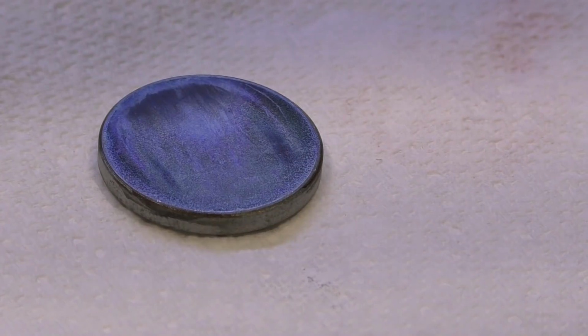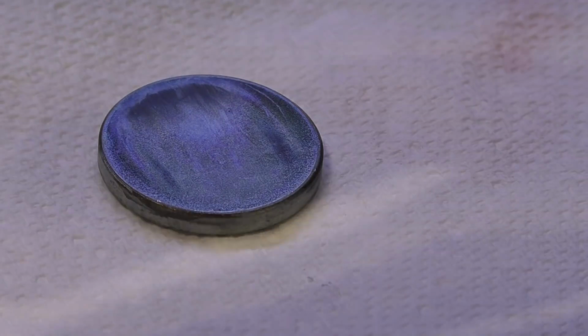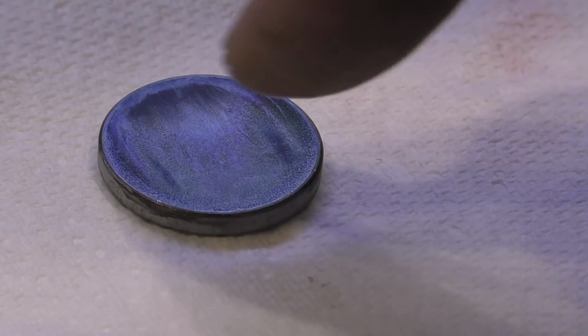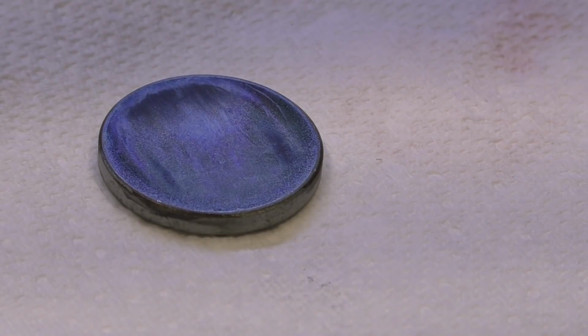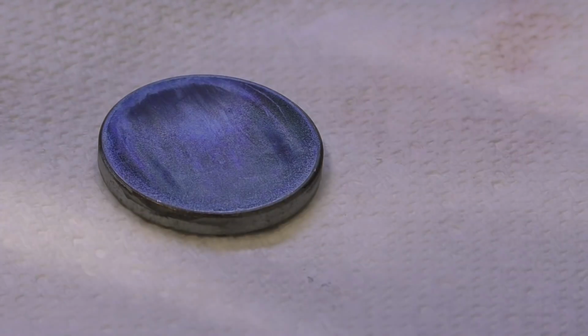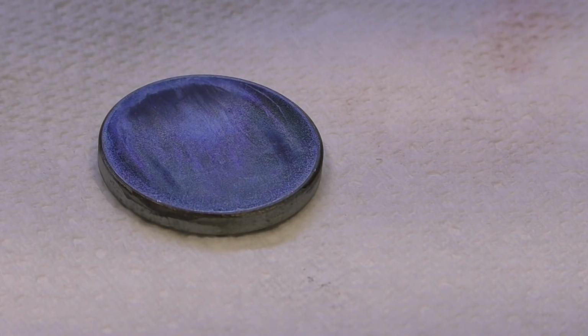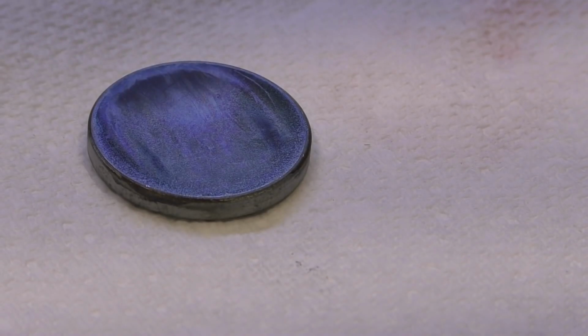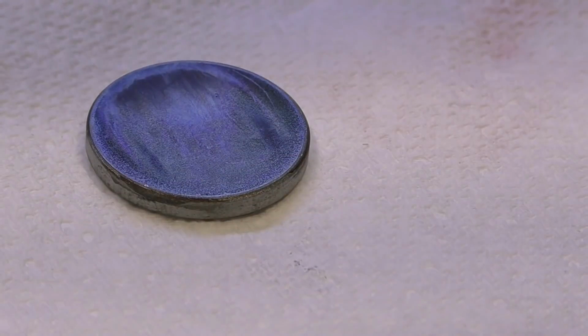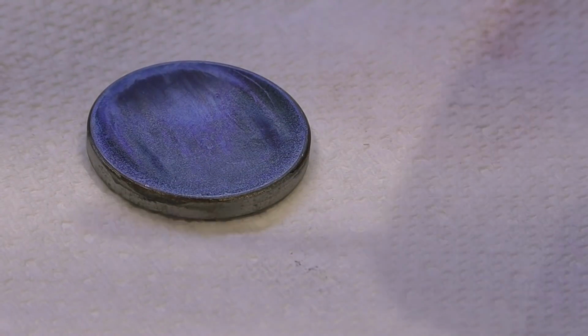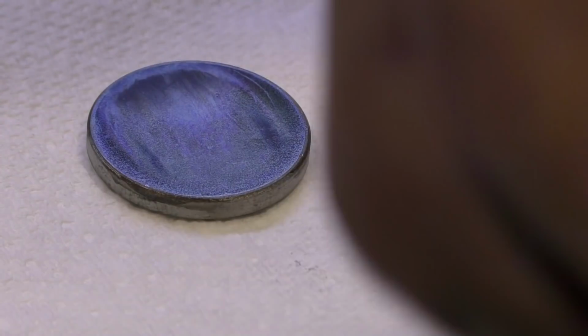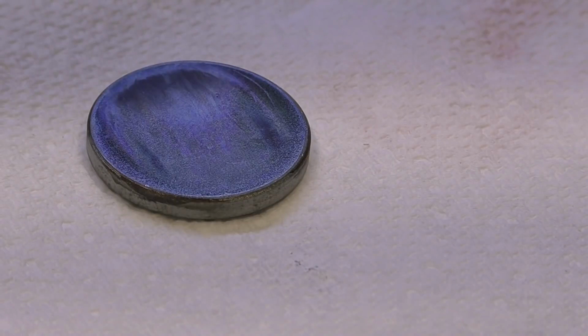These mirrors are molybdenum. They have a naturally reflective surface, crystal structure, which, okay, it gets maybe 1% or so lost if it's tarnished like this, but basically they are consistently somewhere in the region of 96-97% efficient at transmitting infrared light. There are 3 stages that you can go through to clean a mirror. Now, in every case you will need a cotton wool bud and some soft tissue. The cotton wool bud will carry out the cleaning action, and the soft tissue will remove the film that is always left by whatever cleaning agent you use.